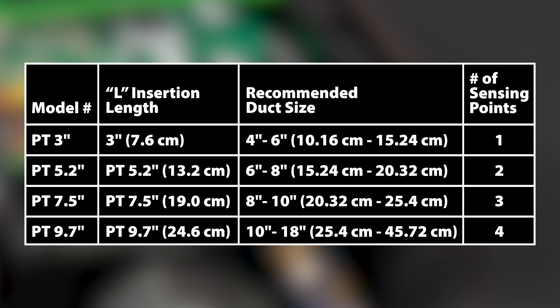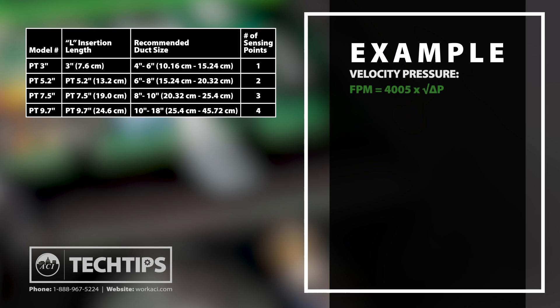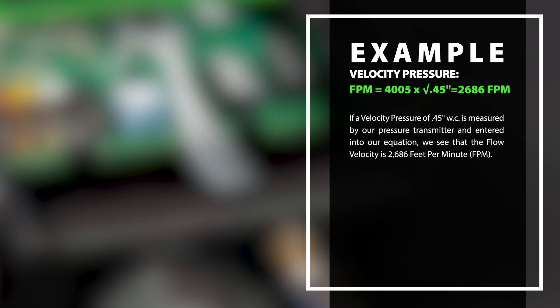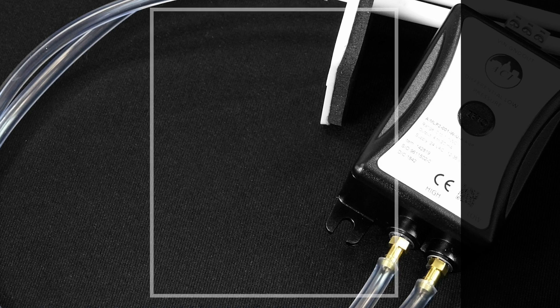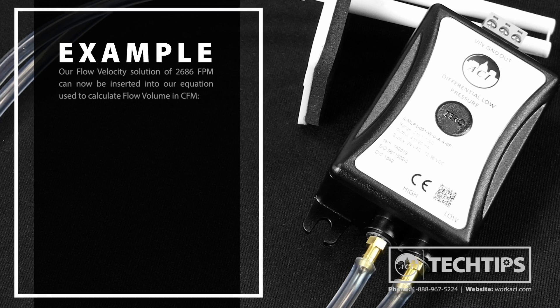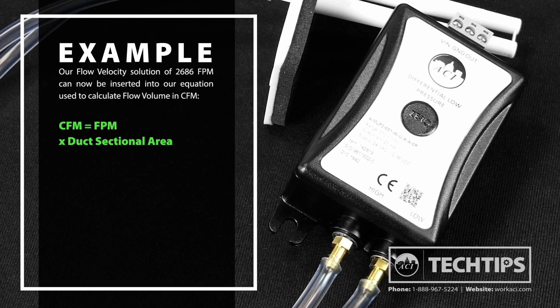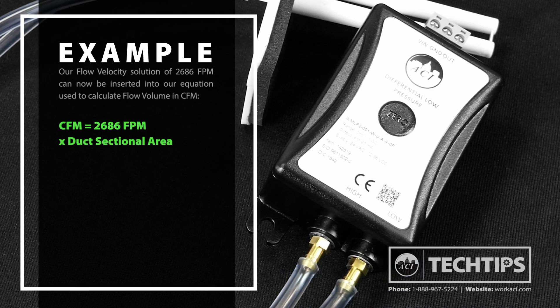The differential pressure transmitter output provides the velocity pressure to be used in our equation. If a velocity pressure of 0.45 inches of water column is measured by our pressure transmitter and entered into our equation, we see that the flow velocity is 2,686 feet per minute. Our flow velocity solution can now be inserted into our equation used to calculate flow volume in CFM.